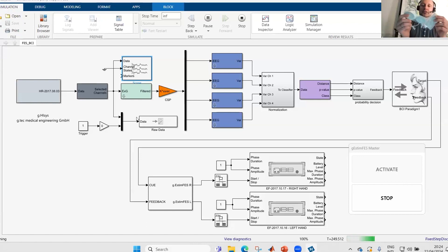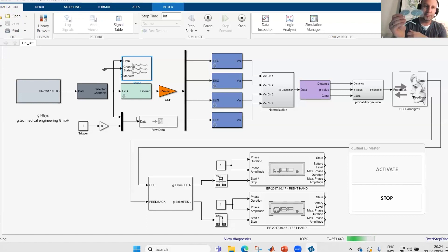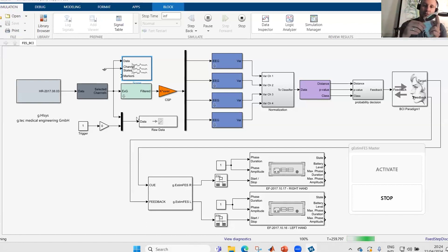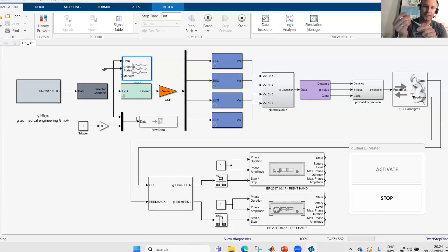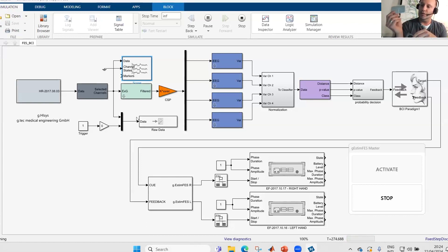For the stimulation electrodes, I use the smaller ones for the upper limb experiment. They are fine for upper limb movements. For lower limb movements, we have also bigger electrodes because the muscles there are bigger, and we have these bigger pads for muscle stimulation of a leg movement — that would also work with this device.